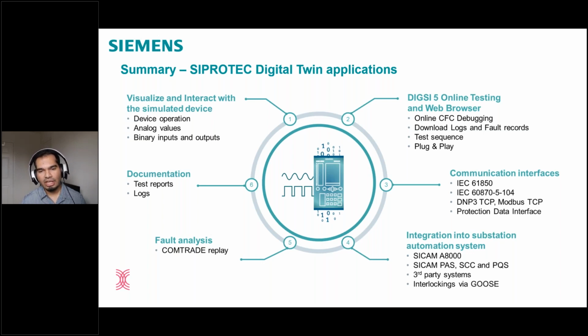You can also communicate to third-party systems. So if you want to do 61850 GOOSE testing with a third-party relay, you can do it, or you can report to a third-party control center or a third-party RTU. You can do it as well. And you can test interlockings of GOOSE between two relays in the cloud, or the relay with an actual physical relay, again by using a VPN bridge.